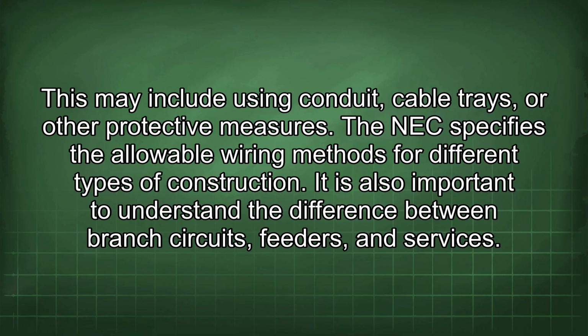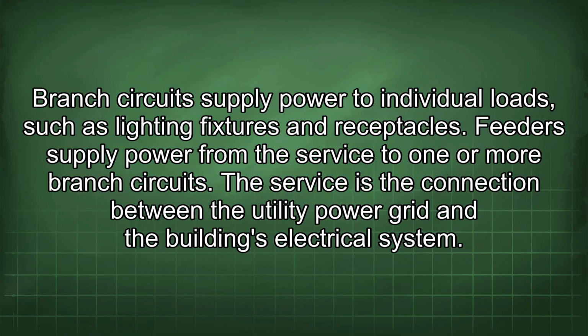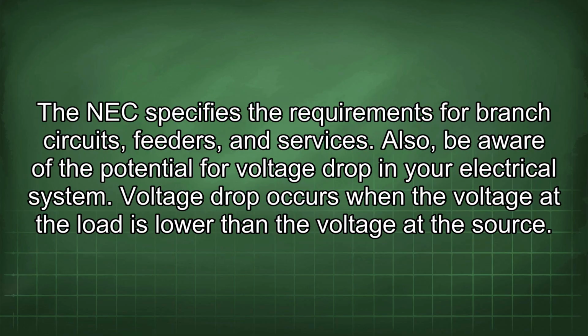It is also important to understand the difference between branch circuits, feeders, and services. Branch circuits supply power to individual loads, such as lighting fixtures and receptacles. Feeders supply power from the service to one or more branch circuits. The service is the connection between the utility power grid and the building's electrical system. The NEC specifies the requirements for branch circuits, feeders, and services.